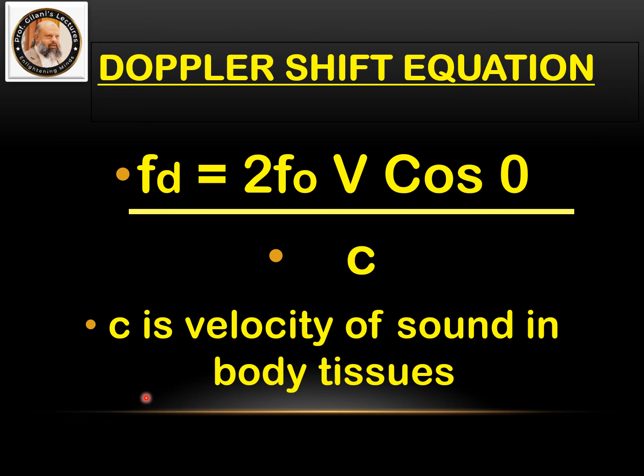So here is the beam, the sounds are traveling, and a blood vessel has RBCs with a specific velocity. They are moving in this direction in this slide, and then the sound strikes the moving RBCs and is reflected back. And this is the angle between the center of the stream of the blood vessel and the center of the transducer. So transmitted sound and received sound.